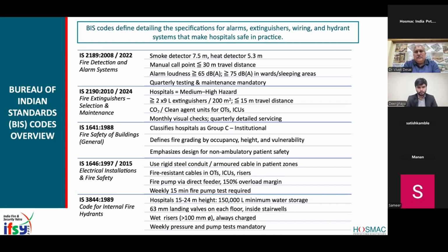So MS conduits are normally preferred because it doesn't get melted during fire because of the high smoke temperatures. But people normally use PVC conduit. So if they use a PVC conduit, they have to use FRLS grade or HMS grade conduits. But MS conduit is preferable. At the same time, armored cables also have to be ZHFR.